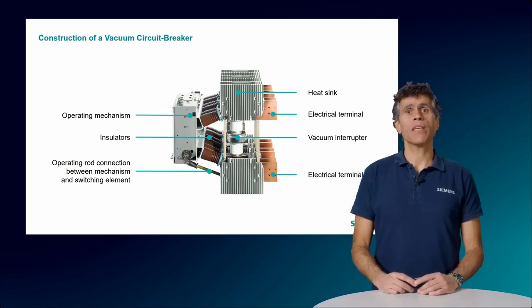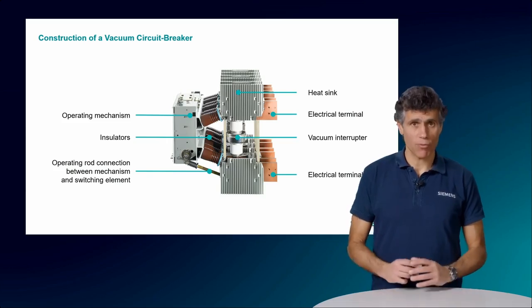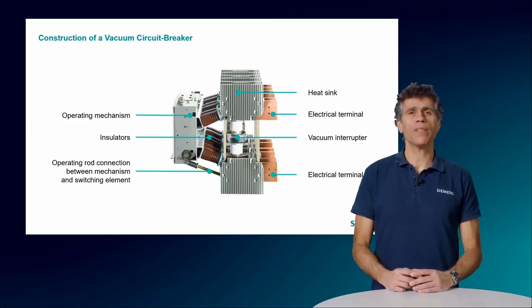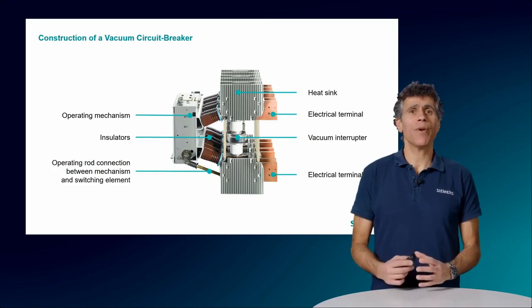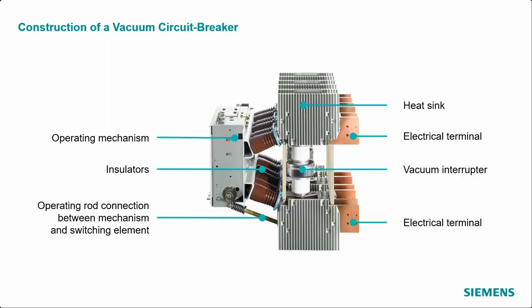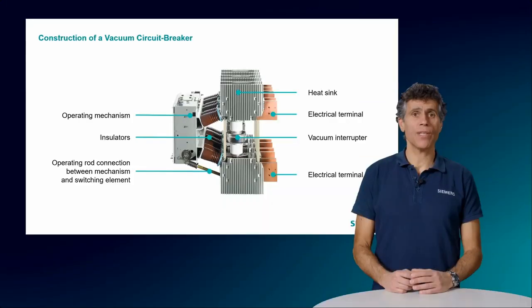Then we come to the place where the magic happens, the vacuum interrupter. This is the core component where the actual circuit breaking occurs. It contains the contact within vacuum. The vacuum eliminates the need for harmful arc-quenching materials, allows for the interruption of arcs with minimal contact erosion and without significant energy waste, and it keeps the contact surfaces permanently clean. In Siemens, our vacuum tubes are maintenance-free and closed for life.